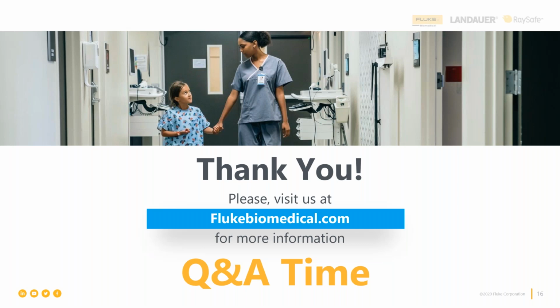Okay, another one here, following on with the blood pressure. Why do we test pressure in PSI and not in mmHg? So the unit of measure that we use for pressure measurement depends on what the pressure is, how it is produced, and why we are making the measurement. In medicine, in clinical use, the units of measure are typically either millimeters of mercury or kilopascal, one or the other. They're typically not any other unit of measure, though there are many other units of pressure that we could use. Millibar, for example, could be used, but it's not. In clinical practice, it's either millimeters of mercury or kilopascals, one or the other.